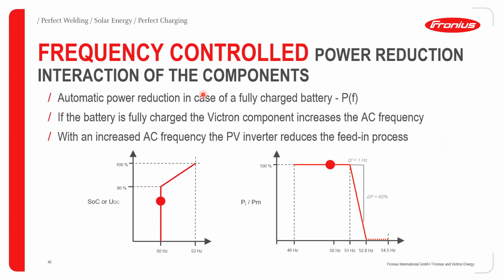The frequency control governs the power reduction interaction of the components. This is automatic power reduction in case of a fully charged battery, or P of f control. If the battery is fully charged, the Victron component increases the AC frequency, and with an increased AC frequency, the PV inverter reduces the feed-in process. So they both work hand in hand in that sense.